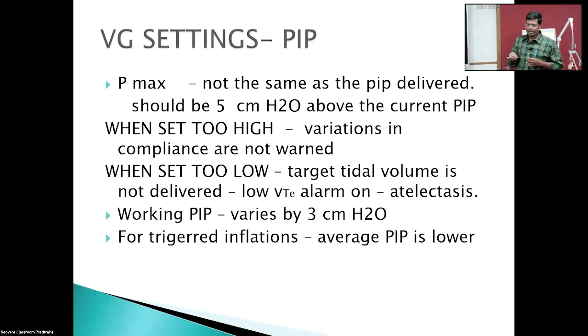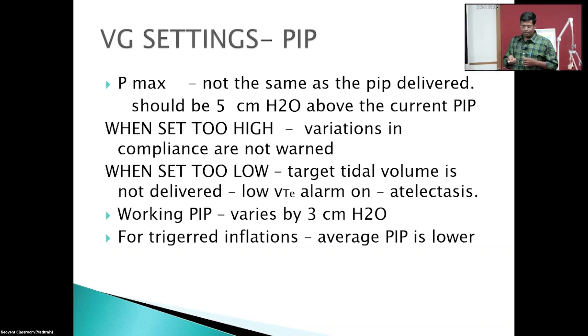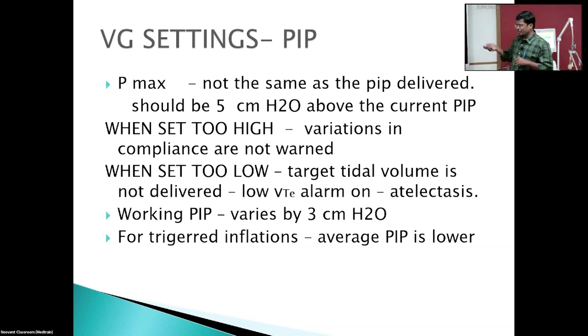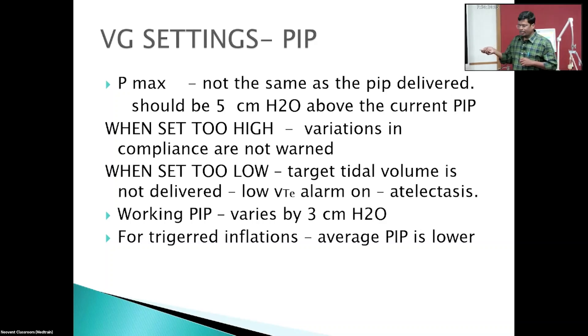When P-max is set too high, changes in compliance may not be sensed. When P-max is set too low and tidal volume requirement is high, a low exhaled tidal volume alarm will trigger, which if not monitored properly may lead to atelectasis. Normally, the working PIP varies by plus or minus 3 cmH₂O, so setting P-max at 5 cmH₂O above the working PIP is appropriate. For triggered inflations the average PIP generated will be lower than for non-triggered inflations.